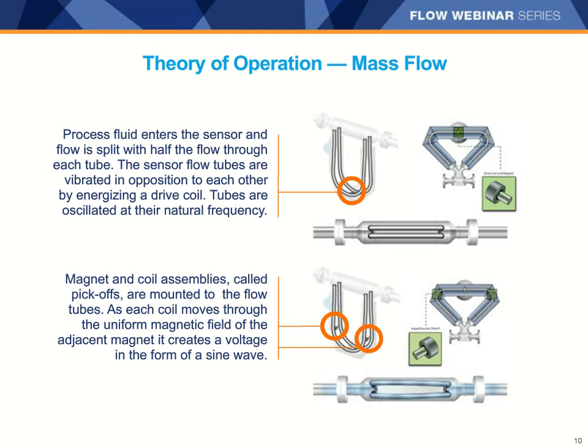The meter tubes are vibrated at their natural frequency with a low voltage DC drive coil that you can see mounted to the tubes in the top cutaway. With no flow, the meter tubes vibrate like you see here in the top diagram. The flow moving through the tubes tries to continue on its path perpendicular to the axis of vibration, resisting the movement. That resistance to the movement causes a deflection of the tubes in the form of tube twist. The tube twist, or angle of deflection from the vibration plane, is measured and converted into a mass flow measurement.